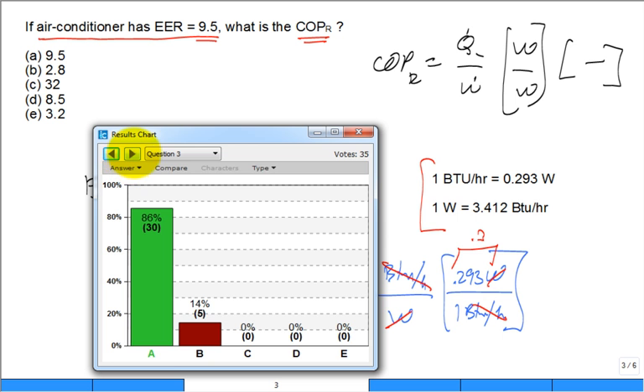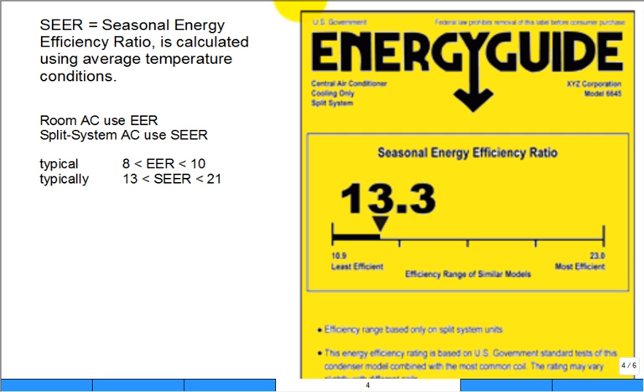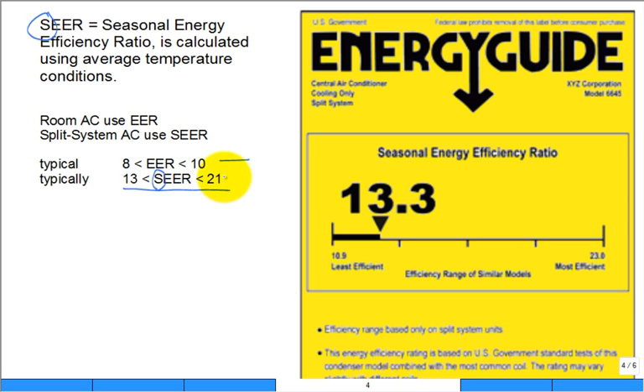More commonly used is the Seasonal Energy Efficiency Ratio, or SEER. Rather than a fixed warm outdoor temperature, SEER uses a varying outdoor temperature. On a mild day the air conditioning system is more efficient — higher efficiency — while on a really hot day efficiency drops. The seasonal average is captured in the SEER rating for split systems or residential systems, and SEER is typically much higher than EER — ranging from 13 up to 20 or 21.